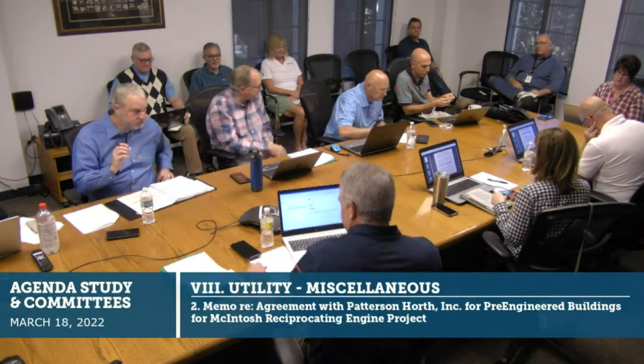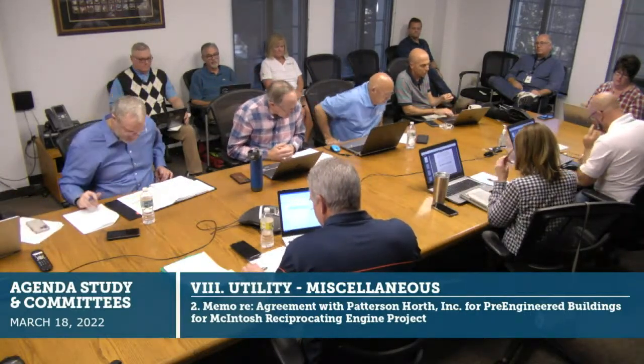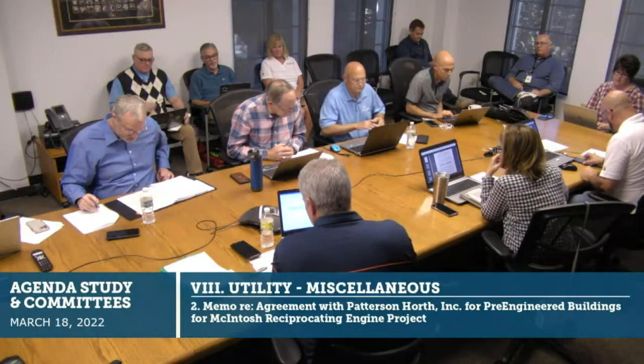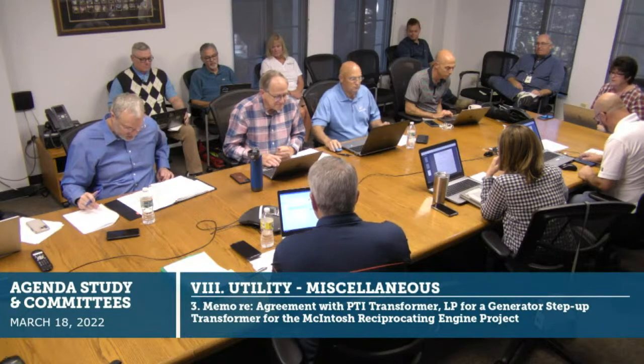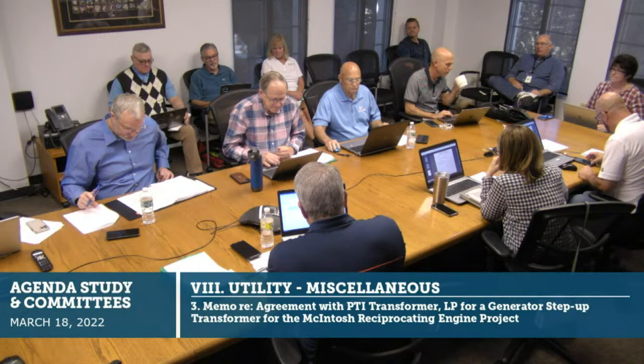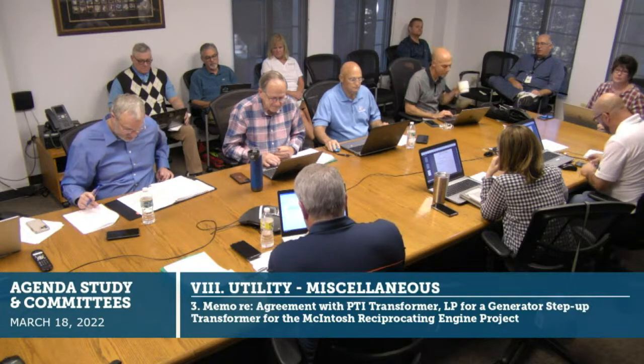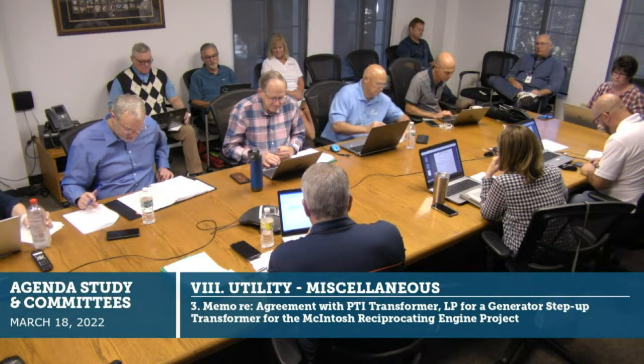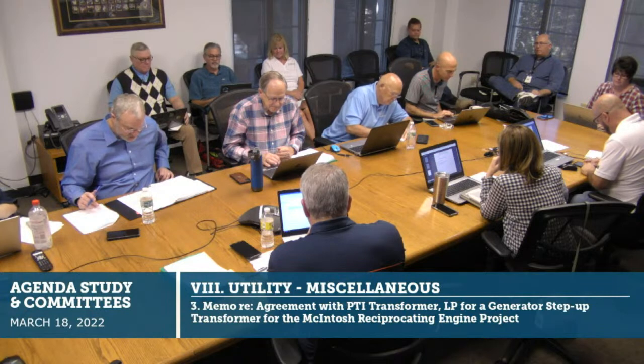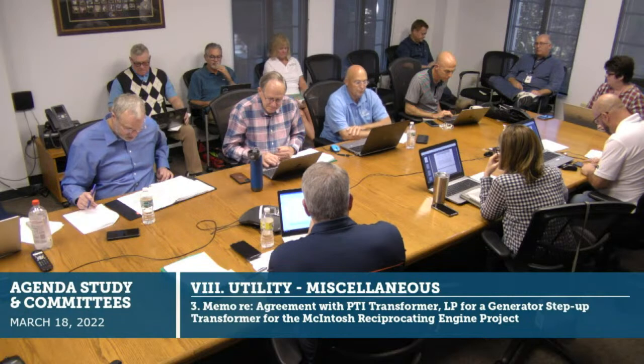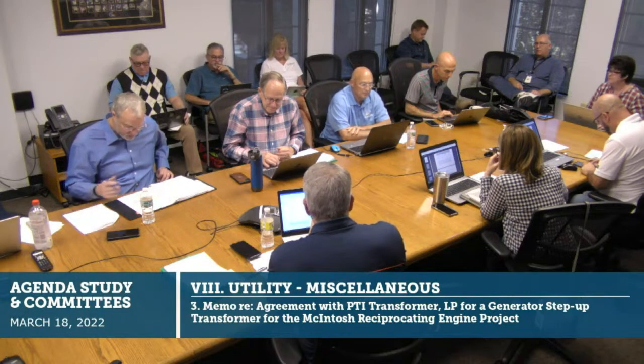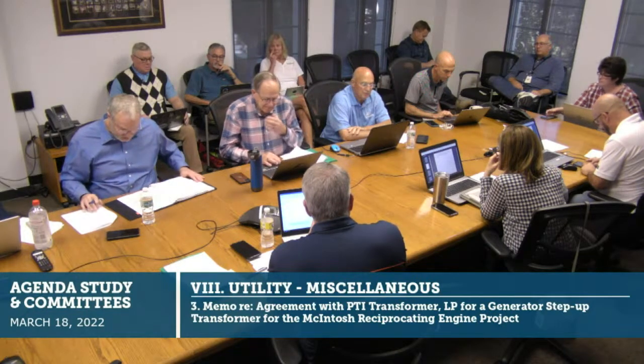Any other questions? All right, the last item is also related to the RICE project—an agreement with PTI Transformer LP for a generator step-up transformer. This will connect the power from the RICE project into the Interlocal 69 kilovolt substation and convert that 69 kV down to 13.8 kV to allow the connection to be compatible.